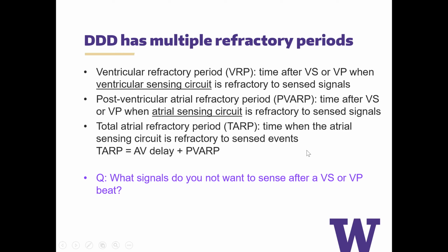Yeah. So one common signal that you actually don't want to sense is T waves. Sometimes on telemetry, people will call you saying the patient is in tachycardia, but when you get there, they're actually not in tachycardia. Even telemetry machines can get fooled. If they count the T wave as a V-sensed event, then you're essentially double counting. In a pacemaker, that becomes important because you can end up inhibiting pacing if the pacemaker thinks it was an intrinsic V-sensed event. So you don't want to oversense T waves.